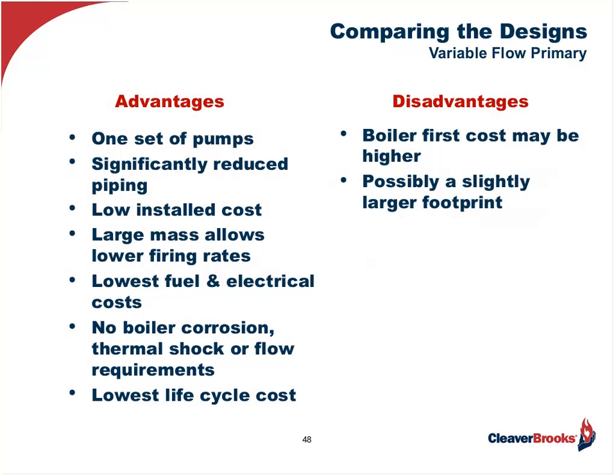Variable flow primary systems, by contrast, are simpler, only one set of pumps, simpler piping, generally a lower installed cost, and the large mass allows no need for a buffer tank and lower firing rates, and lower fuel and electrical costs. Boiler cost may be a little bit higher, but your overall installed cost and life cycle cost will be less. The other drawback is the large mass boilers may have a slightly larger footprint.